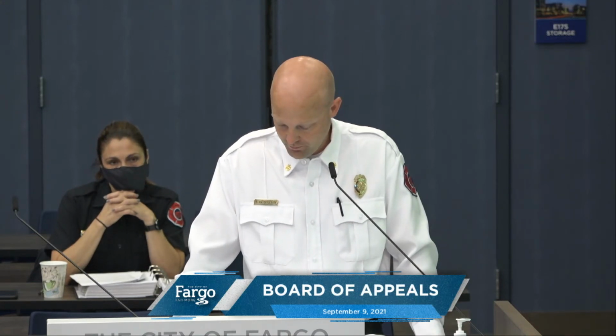A lot of that you'll hear about in 3D printing in the fire code is because they've come up with giant 3D printers that they use in manufacturing, and so it's not just necessarily plastic, it could be metal or other mediums that they're using to make things. Next definition, critical areas. Added a definition for critical areas for the emergency responder radio coverage. And so when we get to that section, it will call those out, and those are areas that would be required to meet radio coverage in a building. Energy storage systems is a new definition to further clarify the requirements of Chapter 12, which is where they pulled together all the energy storage system requirements in the fire code.